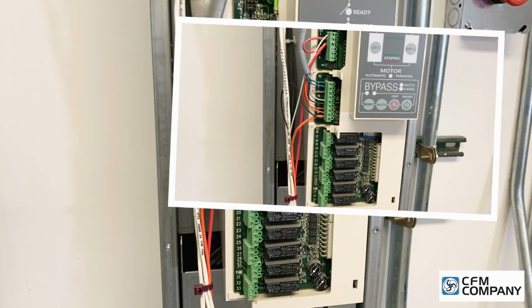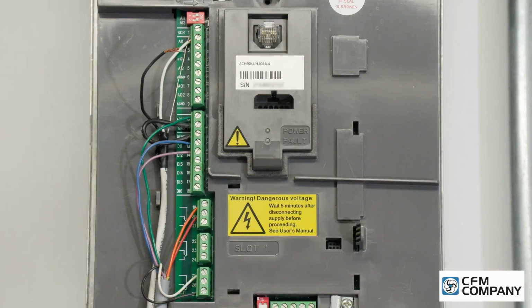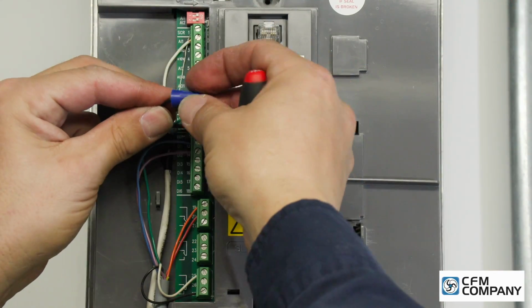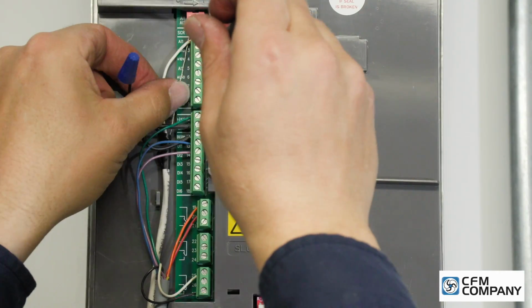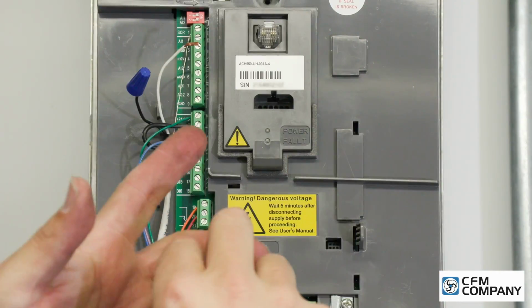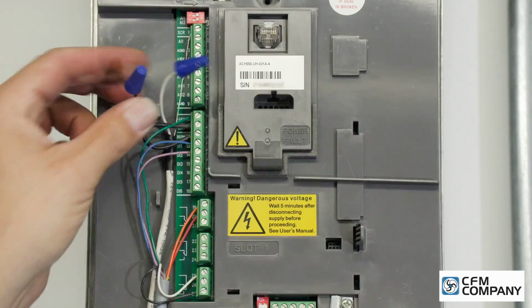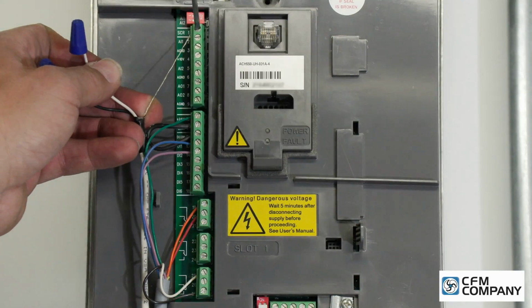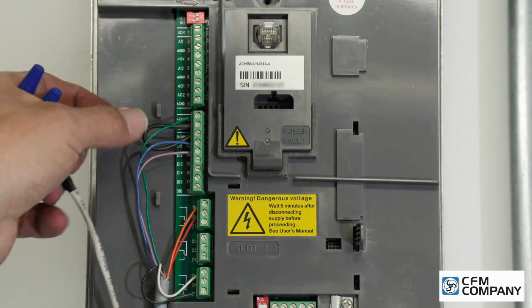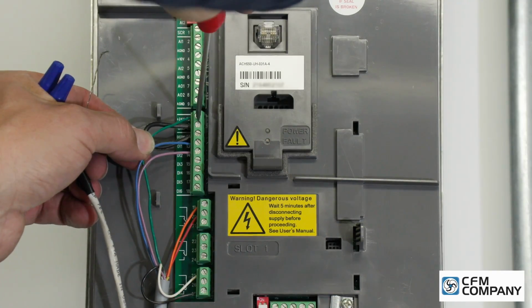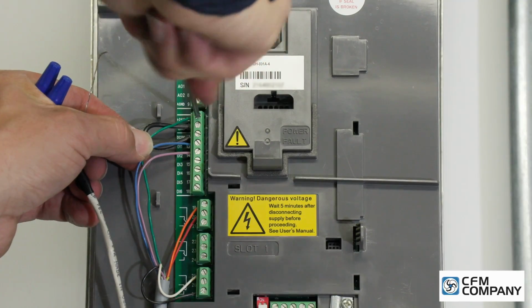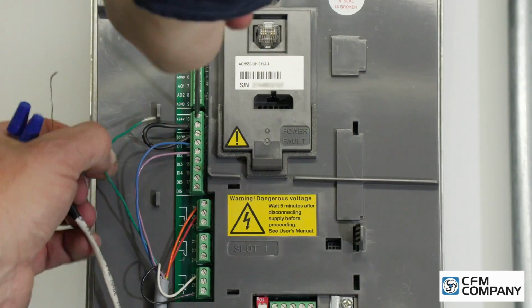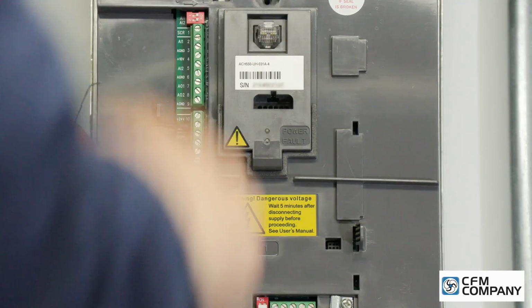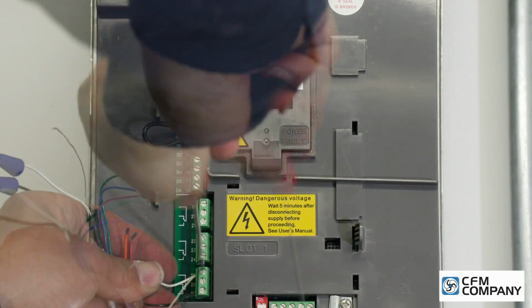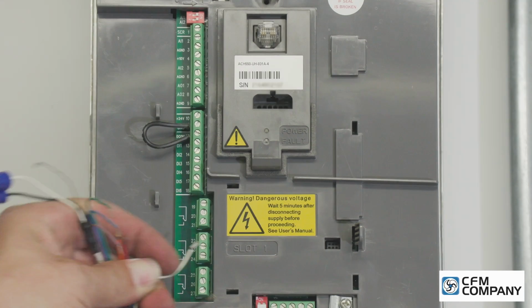Both the control wires landed on the drive and the control wires landed on the bypass. Mark, remove, and cap any analog input and output wires from the VFD. These control wires will be reapplied to the new ACH580 drive. For this example, these are the field wires landed on terminals 1 through 9. The remaining bypass wires in the gray jacket should be removed from the drive. This includes the conductors: green, blue, purple, orange, red, white, and black.